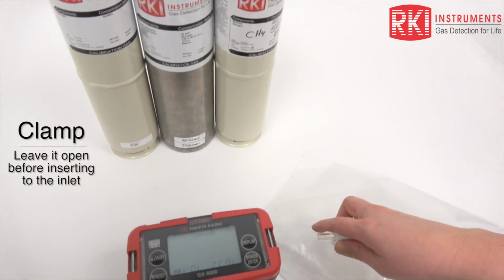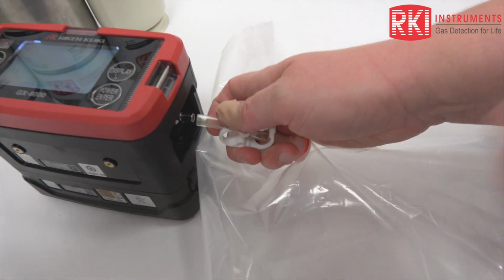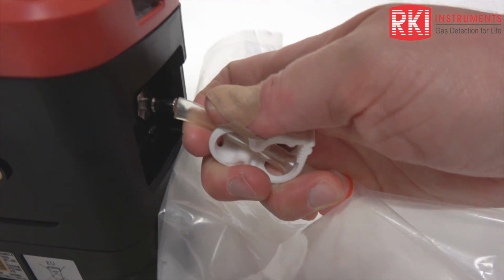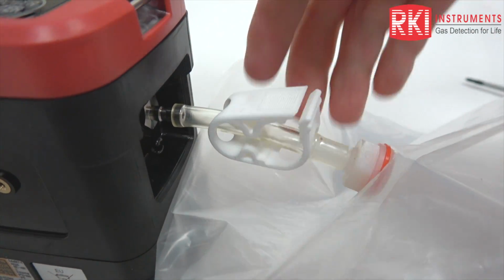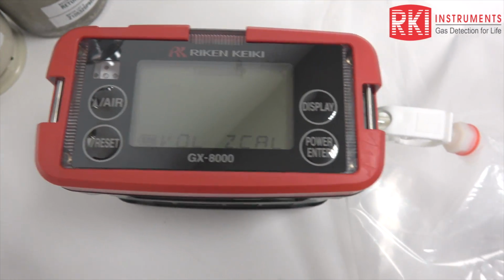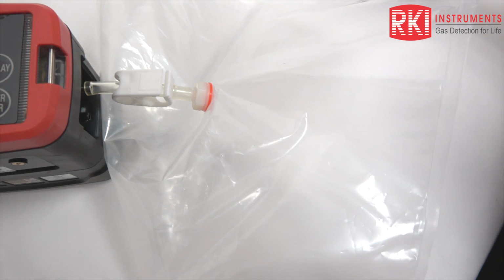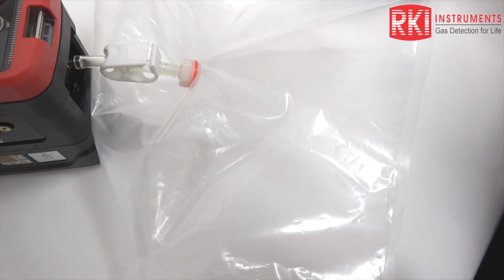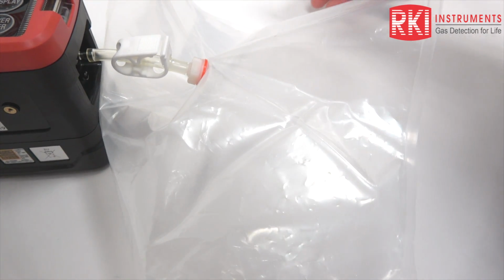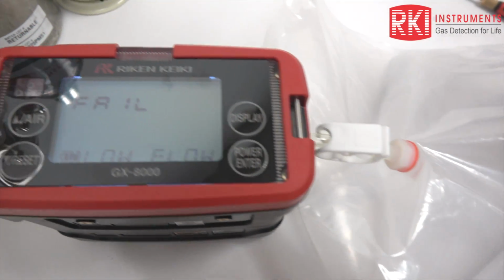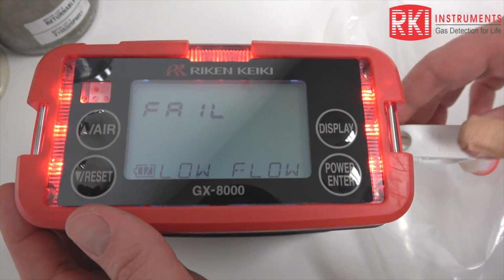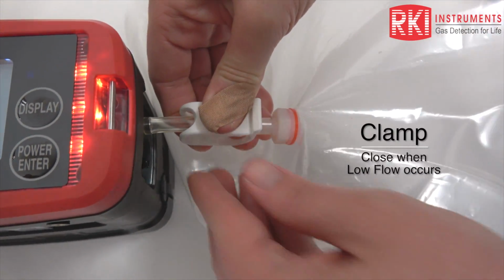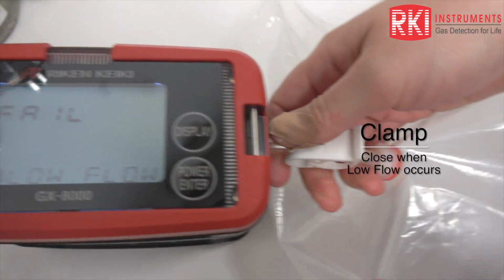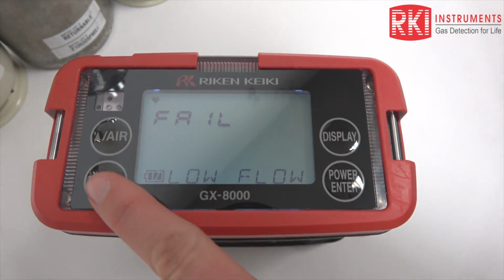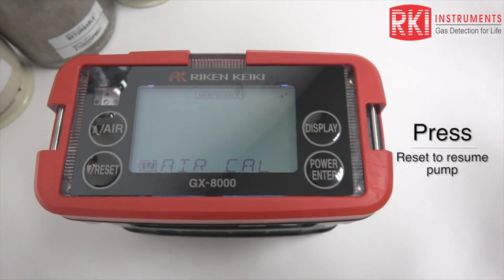I am going to hook it up to my GX8000 inlet because I want to make sure this gas bag is empty. So I'm going to hook it up and I'm going to let the GX8000 draw everything out of that gas bag, whether it was air or other gas. I don't want anything in this gas bag to dilute the sample that I'm going to put in it right now. So you can see my GX8000 went into low flow. I'm going to go ahead and clamp my gas bag shut now that it's empty. Disconnect it from my GX8000 and press reset. Start that pump running again.